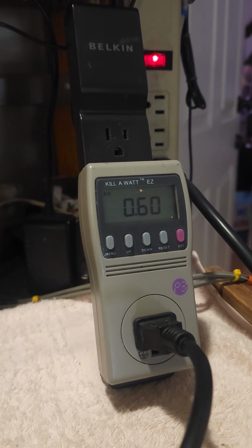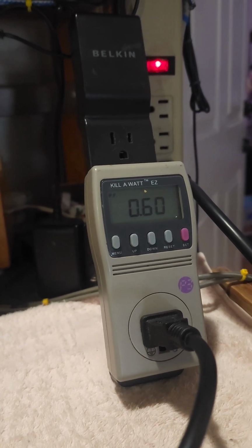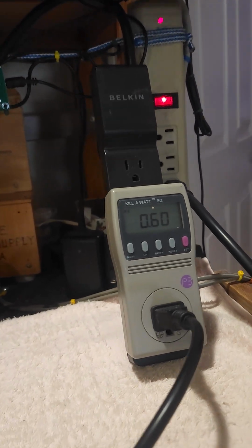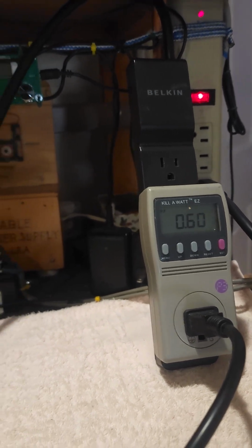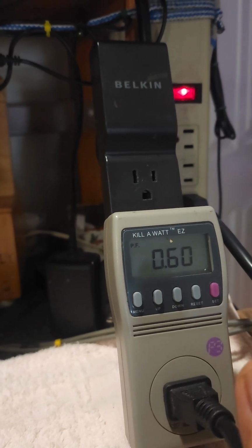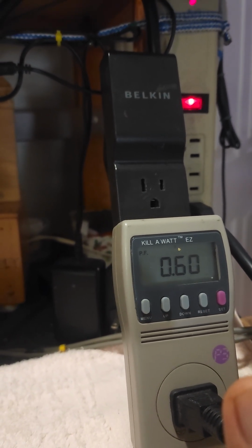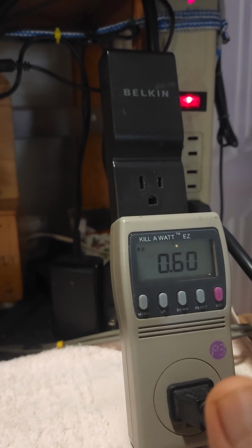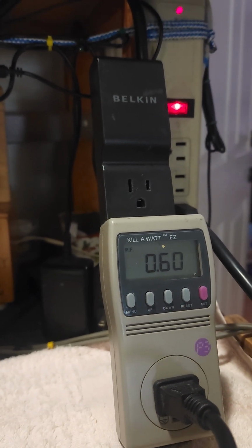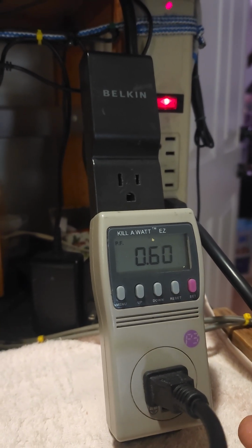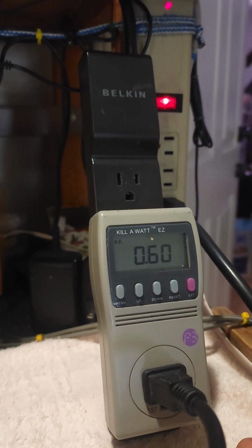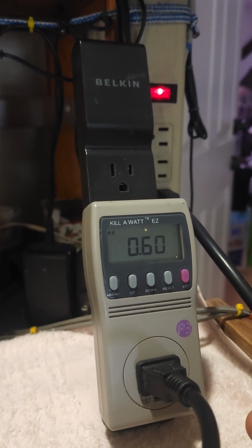So, this is Professor David J. De Los Reyes. What I presented is how to determine the power factor of a small cooler or mini ref using my meter. This meter comprises a watt meter, ammeter, voltmeter, plus a frequency meter, because it measures voltage, current, true power, apparent power, frequency, and power factor, the one we are dealing with for the meantime.